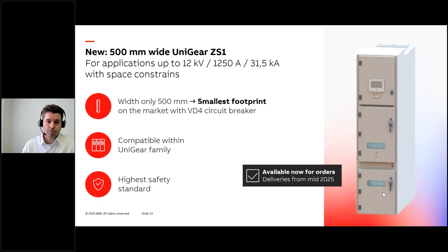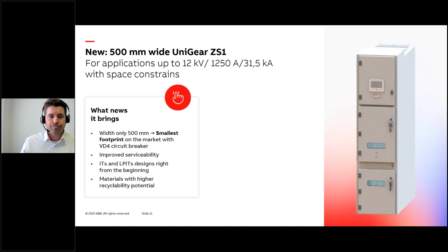The new 500 mm wide Unigear ZS1 brings several new things. That is the footprint, as was mentioned earlier. It is the narrowest panel we have in the Unigear ZS1 product line, equipped with our very well-known VD4 circuit breaker. It has improved serviceability, so the battery is better serviceable from the front side. It comes in two designs, with instrument transformers and with low power instrument transformers. And the fourth new thing is that the materials we are using to form the panel have higher recyclability potential.